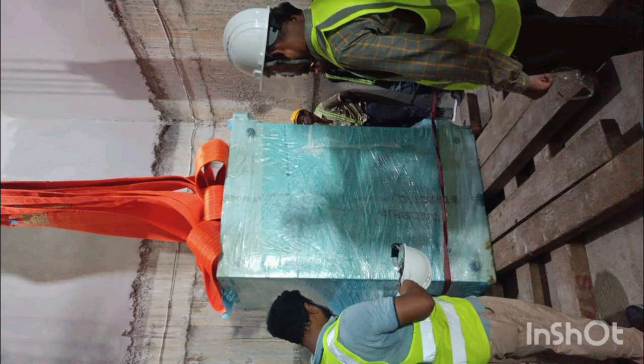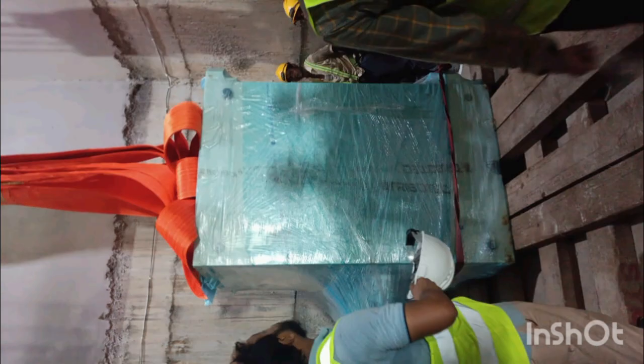Yes, there are lots of advantages and disadvantages of the cyclotron. First I want to talk about the advantages. It is very compact compared to a linear accelerator like a linac, efficient for accelerating particles to moderate energies, and ideal for producing medical isotopes on site. The cyclotron-produced radioisotopes have a very short half-life, so it is important to establish the cyclotron on site. So an on-site cyclotron is very important, and it uses less power compared to a more advanced accelerator.